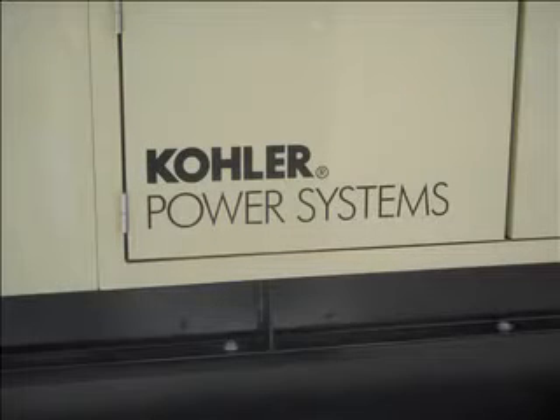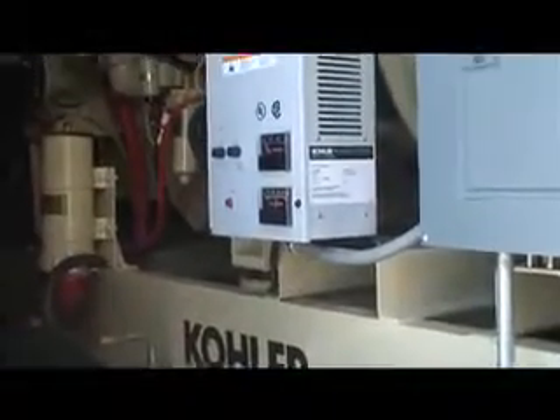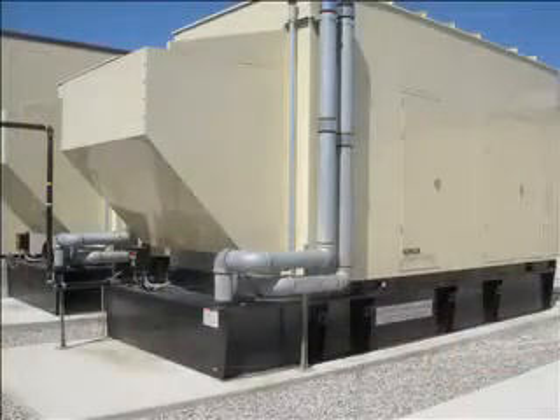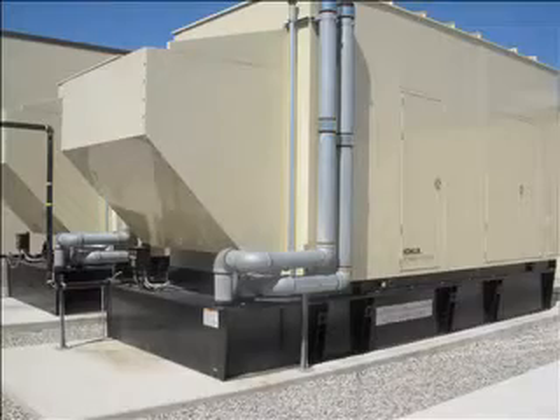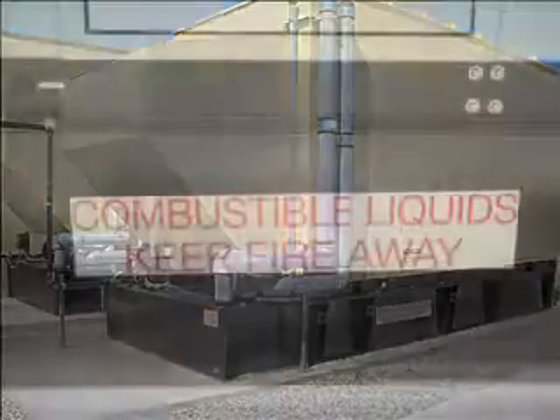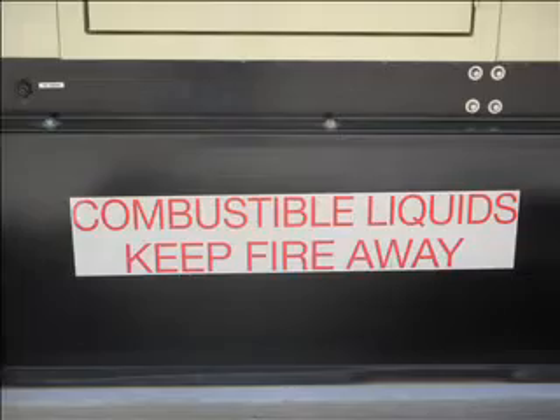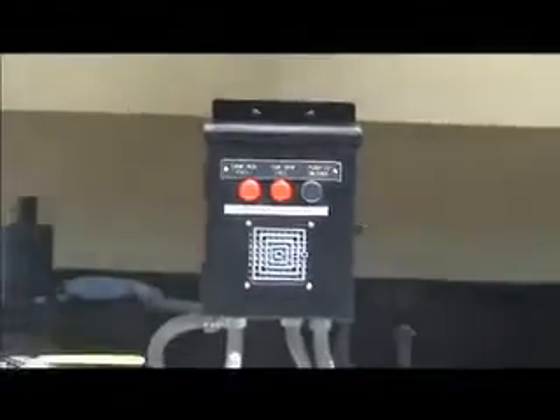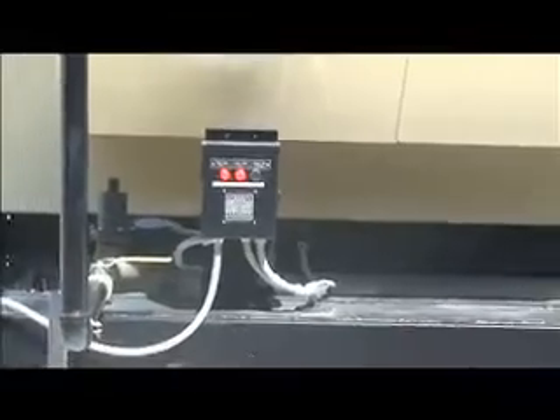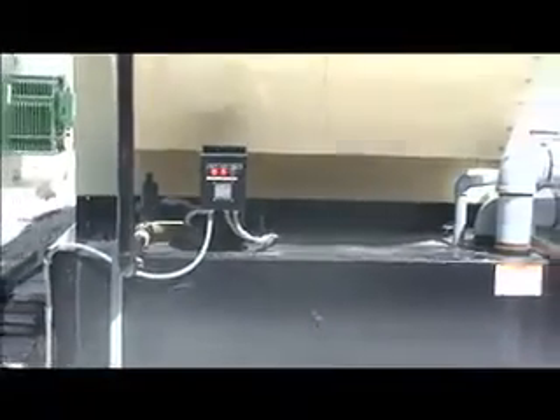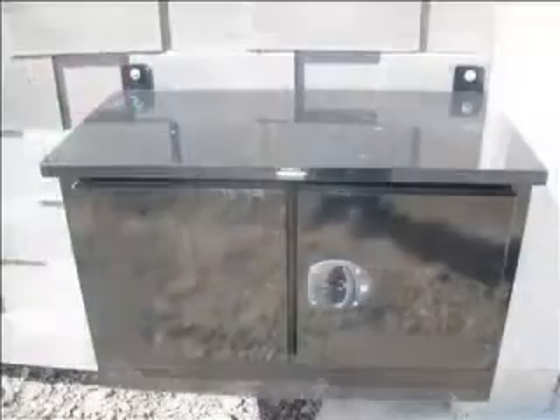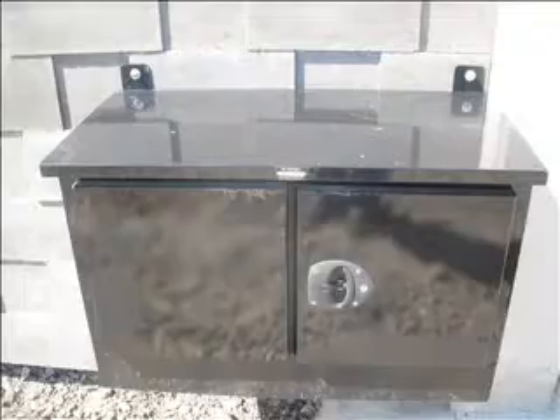These generators are brand new 750 kilowatt Kohler power system plants with locomotive-sized Cummins diesel engines. To support the first of 2 data rooms, there are 2 sets of generator systems for a combined total of 1.5 megawatts of backup power generation. Each of these generators has its own 2,000-gallon diesel fuel storage tank on site, and all of these tanks are interconnected through a remote external refueling supply point. 4 geographically diverse emergency refueling suppliers are under contract to provide 24/7 refueling support.